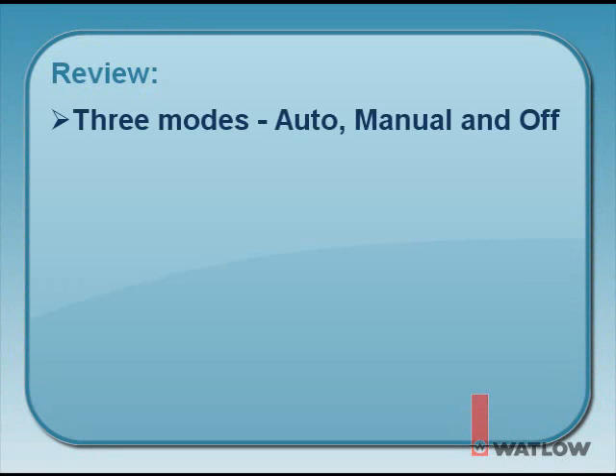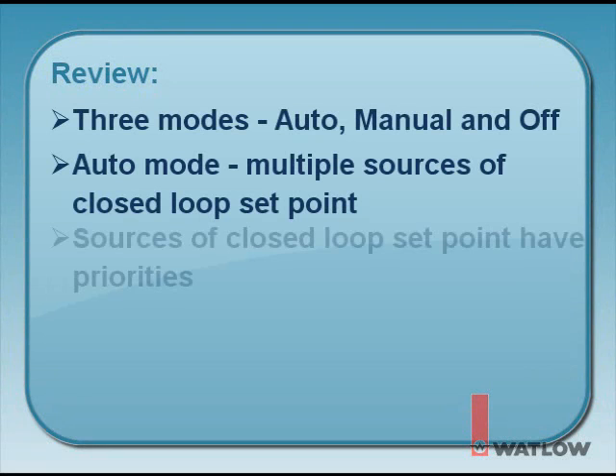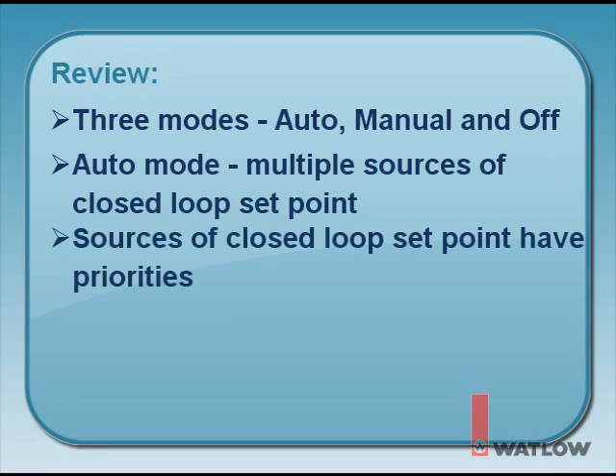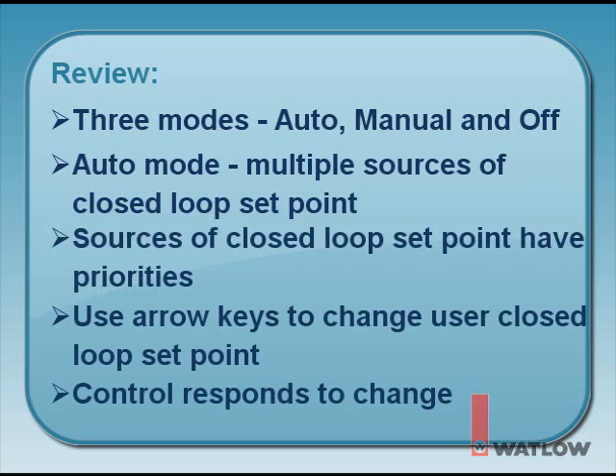Let's review what we've covered. There are three modes of control: auto, called closed-loop control; manual, called open-loop control; and off. Auto mode can have multiple sources for establishing a closed-loop setpoint. These sources have varying priority, meaning some sources override other sources. The up or down key is used to enter a user closed-loop setpoint, and the entry occurs three seconds after the keys are released. The controller responds by adding or removing energy to the load to achieve the desired setpoint.